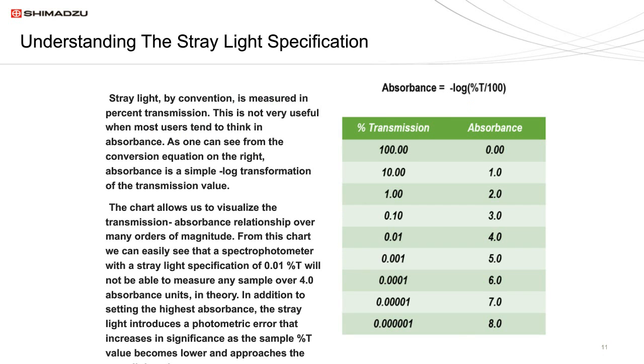This brings us to talking about the stray light specification. Stray light is defined as any light in the instrument not at the wavelength that the monochromator is set at — this includes light leaks, reflections, but most importantly, imperfections in the diffraction gratings. Almost all instruments use diffraction gratings, and small imperfections in the lines of those gratings lead to scattered stray light. Stray light sets the upper limit of how high in absorbance you can measure. Stray light is always given in percent T, and the logarithmic relationship between transmission and absorbance determines how stray light affects performance.